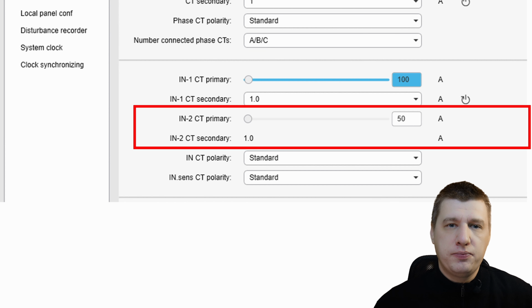IN-2 CT primary. We already covered standard phases and earth fault settings. Now we're looking at the In2 CT primary settings. This is for the special ops of earth fault detection, the very sensitive earth fault input. Let's look at how that works. In the P5, In2 refers to the very sensitive earth fault VS input. While the standard In1 input handles typical ground faults, In2 is designed for detecting tiny current leakage that standard transformers might miss. You'll find those wires connected to terminals A15 and A16 in slot A.